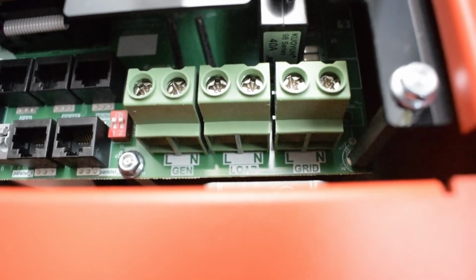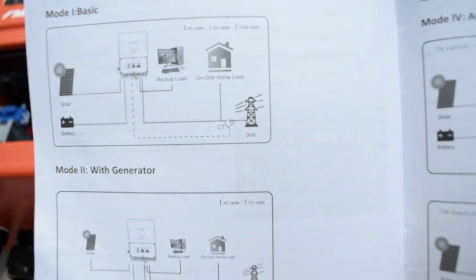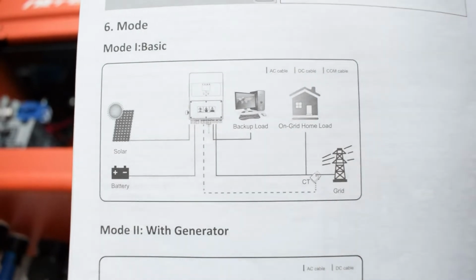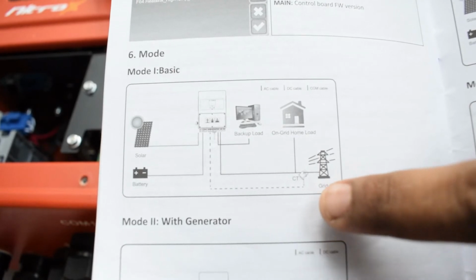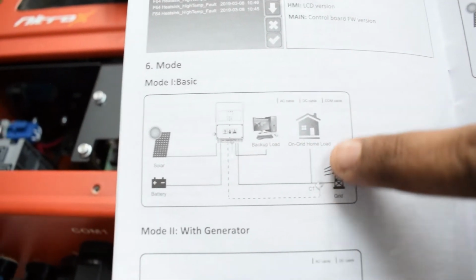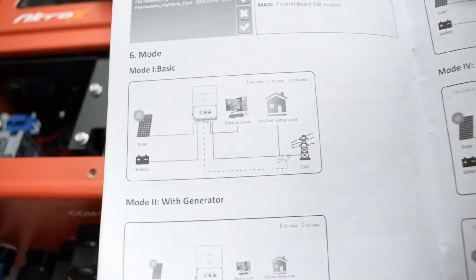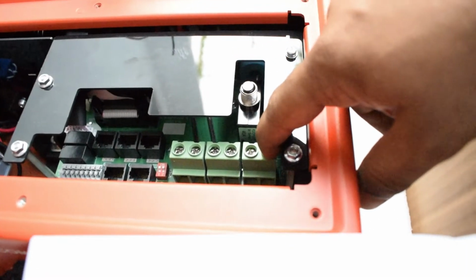For example, we have 4 modes, and 3 modes of the 4th mode are explained in the manual. Let me show you. Yes, these are the modes. The first one is the most basic mode, in which we connect solar, battery and connect CT with the grid, and connect the whole load with the grid, and the major load which can be utilized for battery backup we connect with the backup load. So only 2 functions will be utilized, one is the load and one is the grid. Generator function will not be available in basic mode.